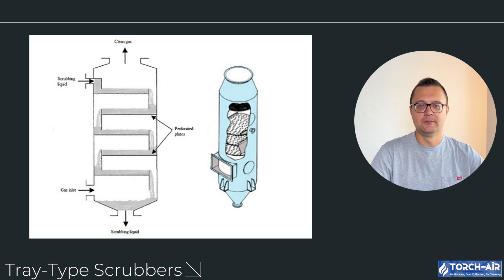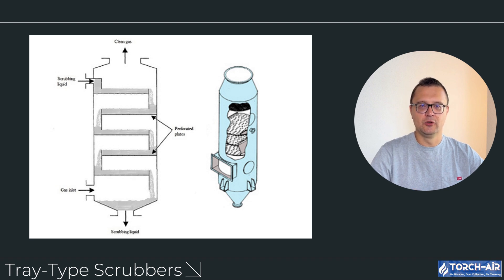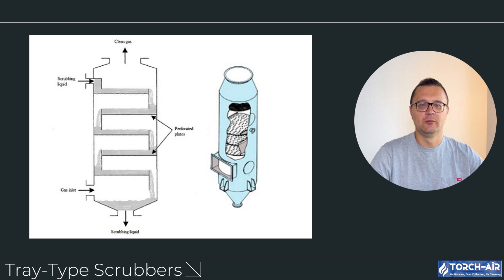In tray-type scrubbers, instead of using nozzles to spray liquid, the gas passes through perforated trays or plates that hold a liquid film. The gas bubbles up through the liquid, creating intense gas-liquid contact. Best for applications requiring high-efficiency gas absorption without the use of nozzles. Trays provide consistent gas-liquid interaction without requiring high-pressure pumps or nozzle maintenance, and are particularly useful in chemical scrubbers dealing with gases like ammonia or sulfur oxides. Consideration: tray scrubbers can be more expensive to install and maintain due to the complexity of the tray system.